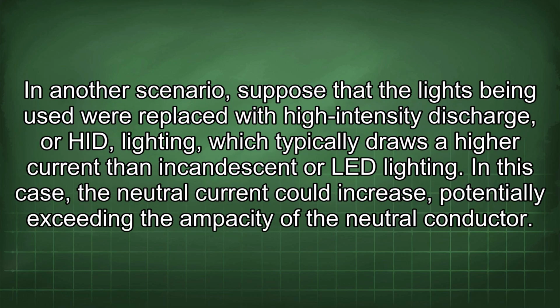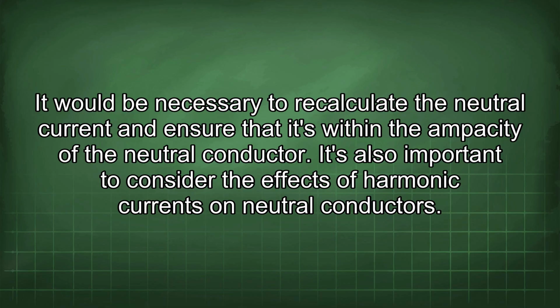In another scenario, suppose that the lights being used were replaced with high-intensity discharge, or HID, lighting, which typically draws a higher current than incandescent or LED lighting. In this case, the neutral current could increase, potentially exceeding the ampacity of the neutral conductor. It would be necessary to recalculate the neutral current and ensure that it's within the ampacity of the neutral conductor.